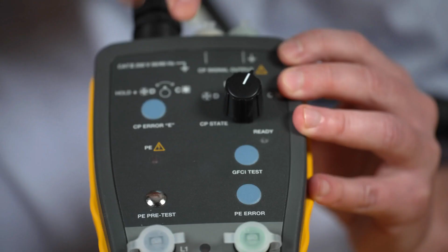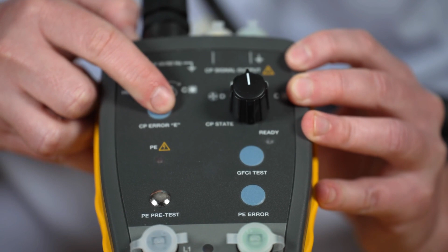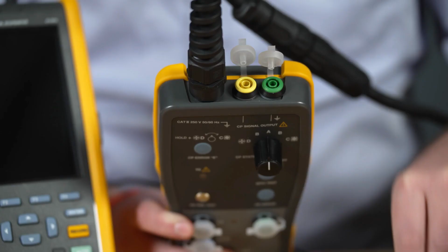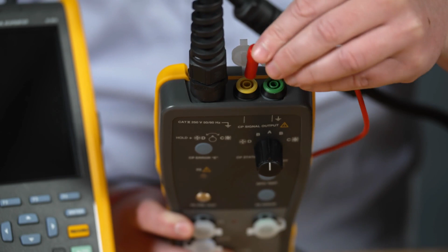You can also test GFCI trip time and leak current. Troubleshoot and simulate control pilot and PE errors through the simple press of a button. Check if the charging station cuts off the output voltage for each error separately. For more in-depth measurements, you may also want to connect a Fluke scope meter. We always recommend to use a Fluke 124.